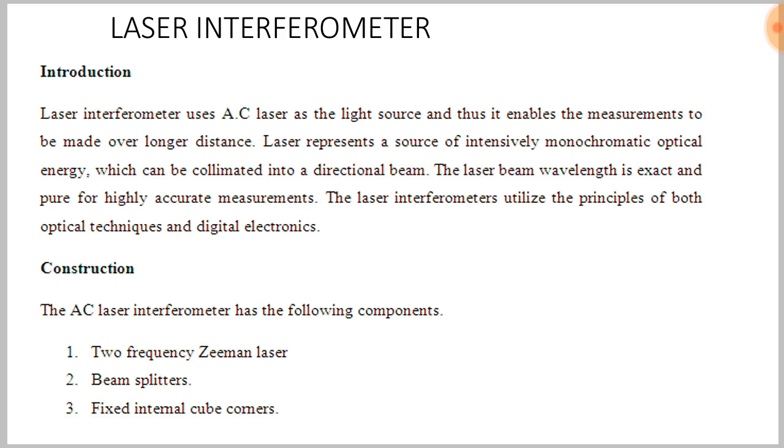Construction: The AC laser interferometer has the following components: two frequency Zeeman laser, beam splitters, and fixed internal cube corners.